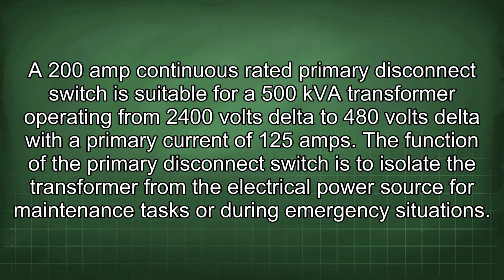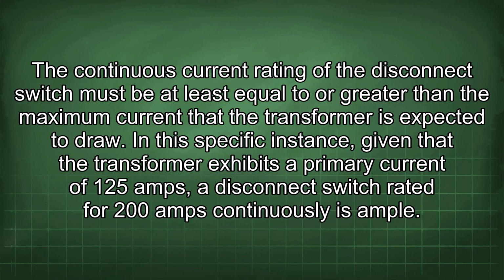A 200 amp continuous rated primary disconnect switch is suitable for a 500 kVA transformer operating from 2400 volts delta to 480 volts delta with a primary current of 125 amps. The function of the primary disconnect switch is to isolate the transformer from the electrical power source for maintenance tasks or during emergency situations. The continuous current rating of the disconnect switch must be at least equal to or greater than the maximum current that the transformer is expected to draw.